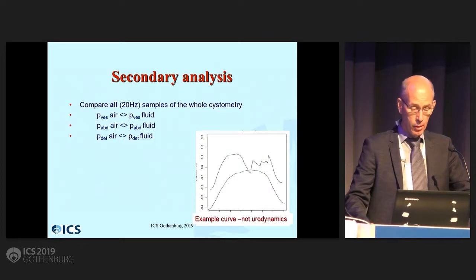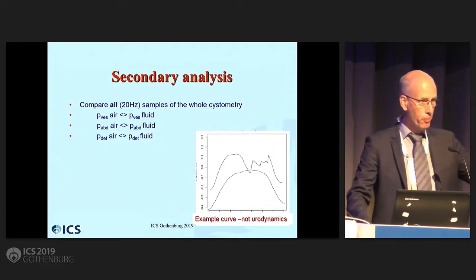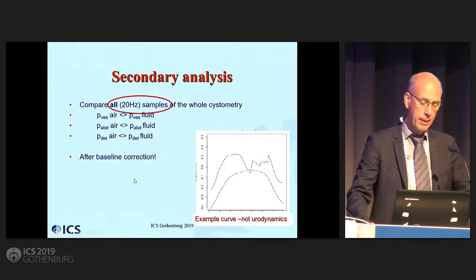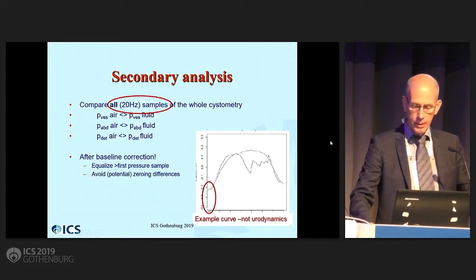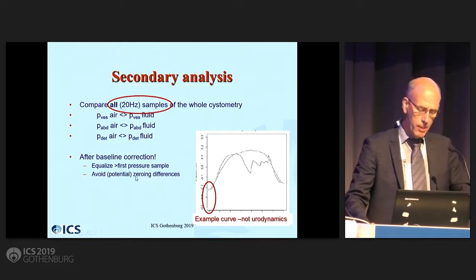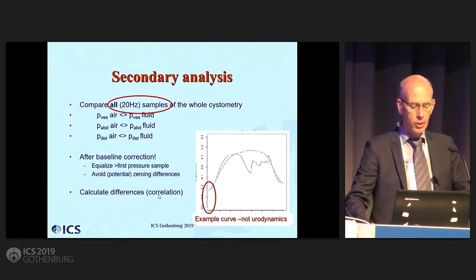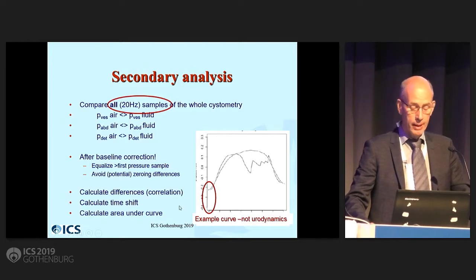After good zeroing, I decided to compare all the samples of the whole cystometry — more than 10,000 samples per pressure trace. I was going to compare vesical versus vesical, air versus fluid, et cetera. And then I had those baseline differences. I said, if I correct those baseline differences, what's going to happen? What differences are left? So I equalized those — this is effects after zeroing: calculate differences, correlation, and calculate time shift. And area under the curve. That's what I did.